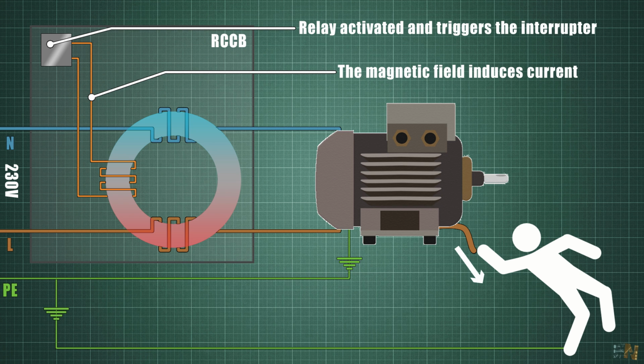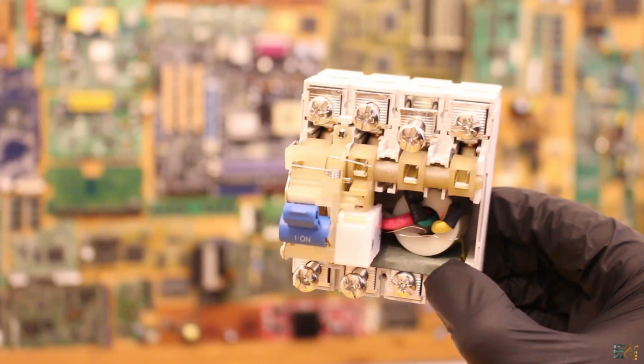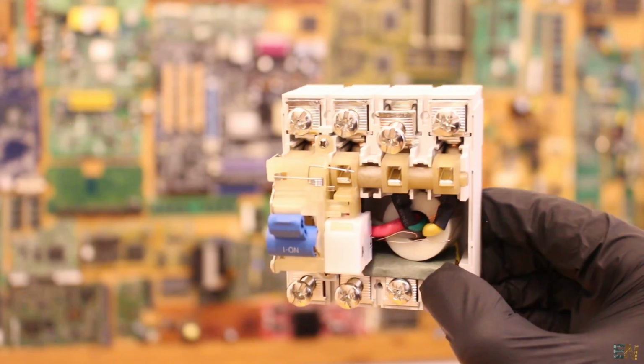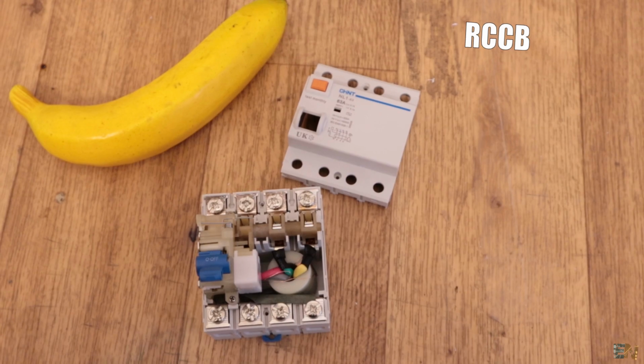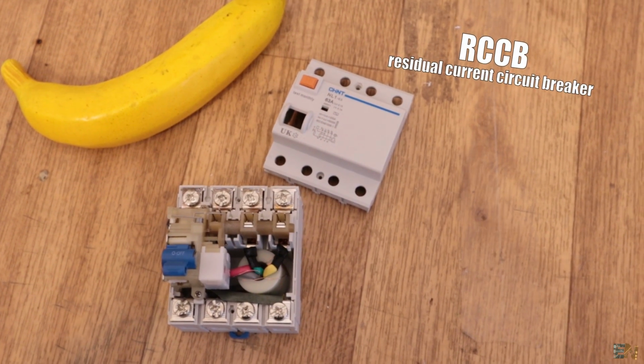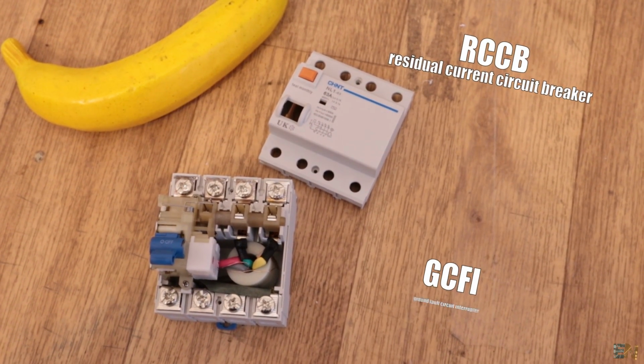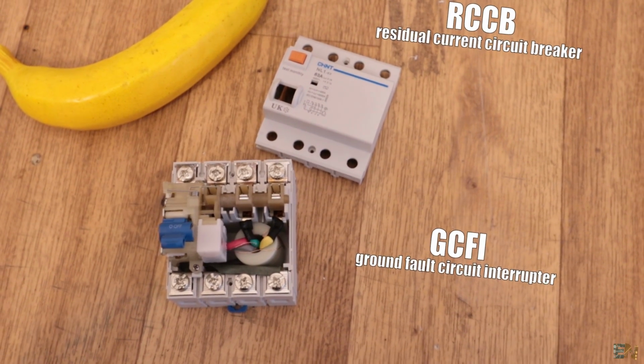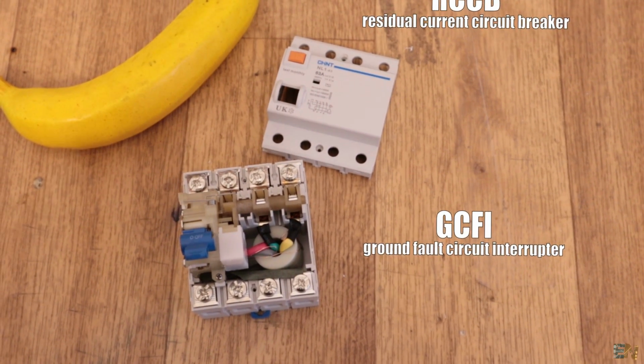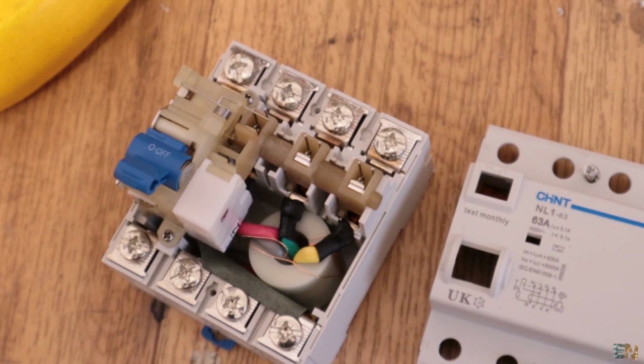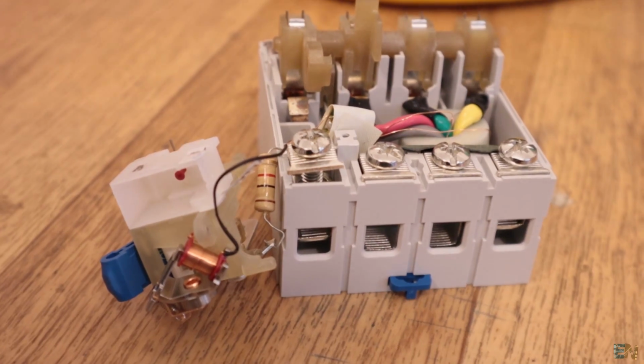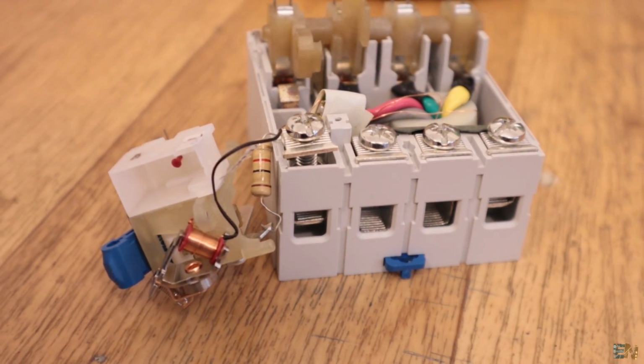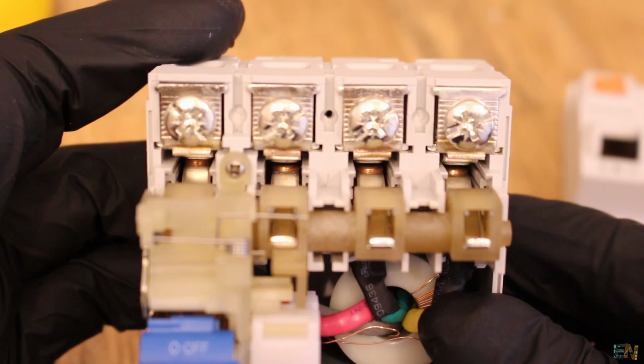So each time we have a current leak that is not getting back to neutral, the RCCB will jump and save our lives. That's why this is called a residual current breaker, because we have a residual current flowing in the wrong way. RCCB is the name that we use in Europe, but in the United States, this device is called GFCI, or ground fault circuit interrupter, and it's kind of the same. All we have to do is to detect a small current difference between the input and the output, and when that occurs, it means that the current is going in the wrong place.